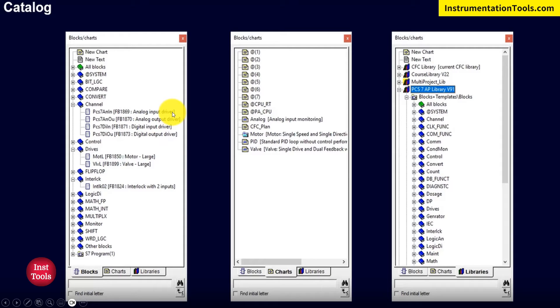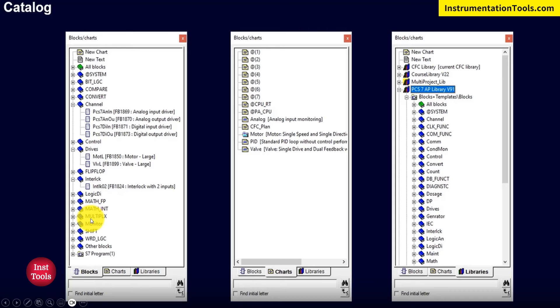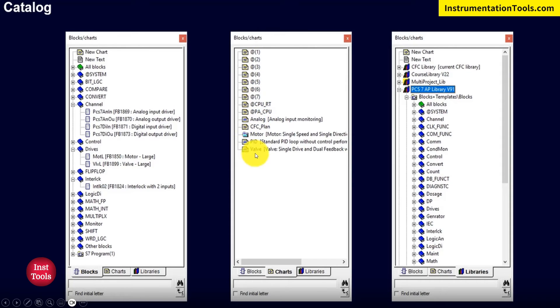In the Catalog, we have three areas: Blocks, Charts, and Libraries. The Blocks area is a simple navigation to already-used FBs in the CFC editor — if you've already imported a block, you can find them in corresponding areas like channels, drives, controls, or monitoring for analog variables. The Charts area allows you to implement a chart connection or derive a CFC as an FB — all CFCs created in the program are listed here. The Libraries area contains numerous FB types; to use any, navigate here and drag the block into the CFC area.